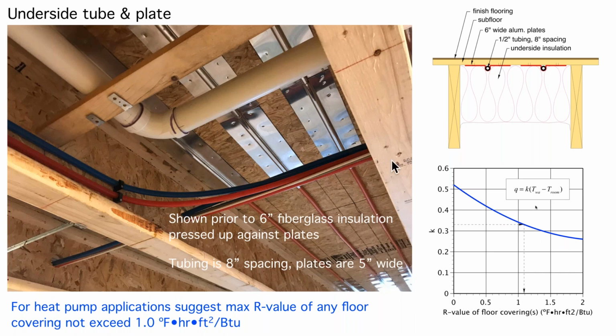Now, there is a graph over here and a formula. I won't spend a lot of time on it, other than saying you could calculate your water temperature requirement. This is based on, again, 8-inch tube spacing, and it's a trade-off between the R value of the floor covering, what's on top of this subfloor. The subfloor is assumed to be 3/4 inch oriented strand board or plywood, with whatever you're going to put on top of that for a finished floor. The R value here gives you a value of K. You put that into the formula, and again, you have average water temperature minus room temperature.